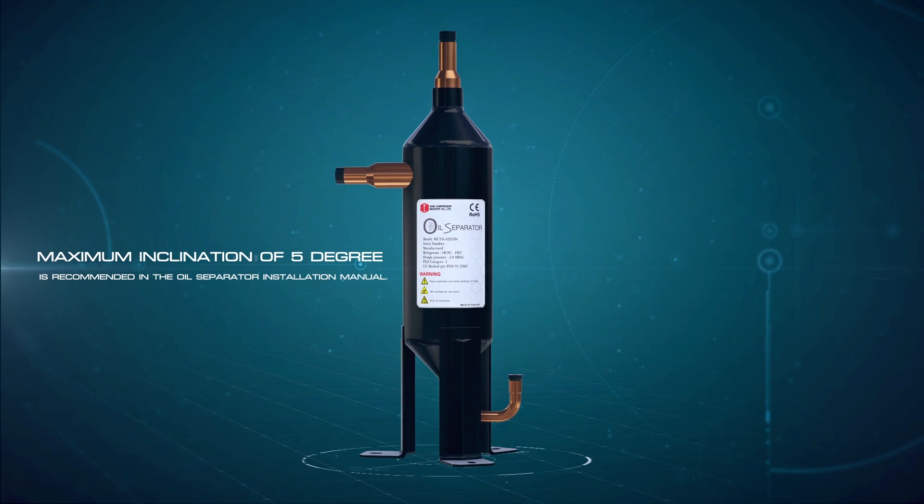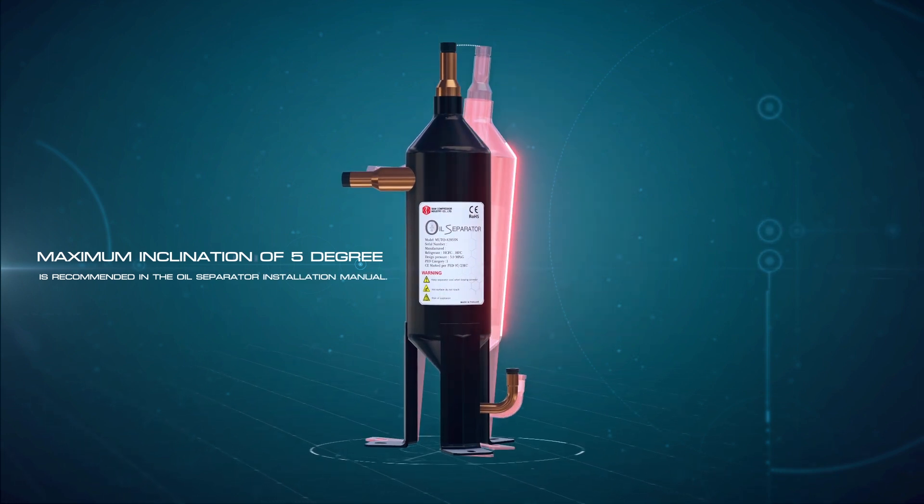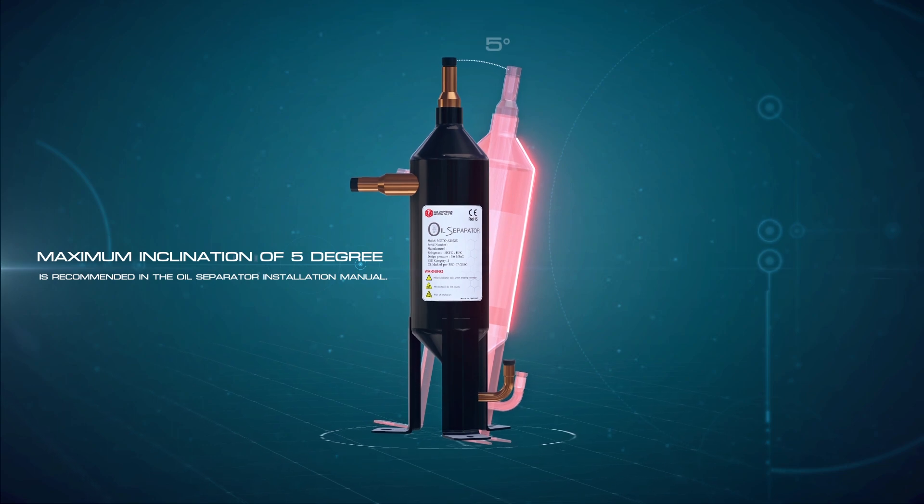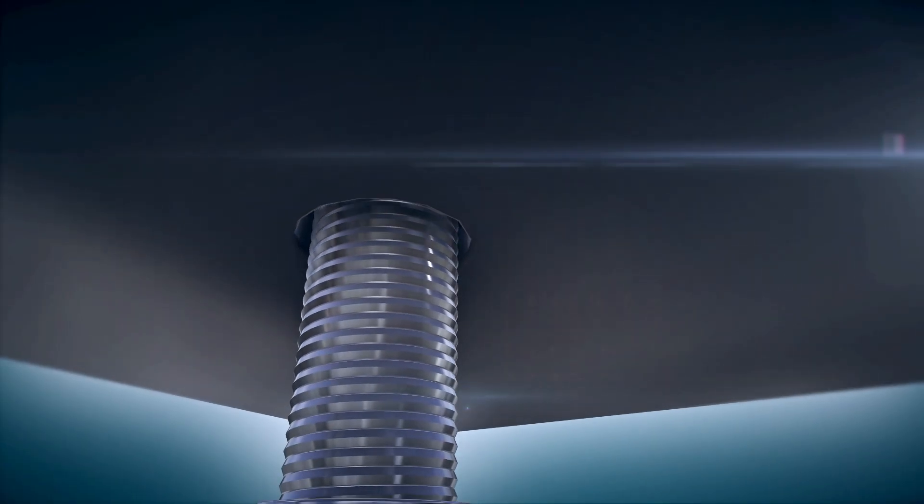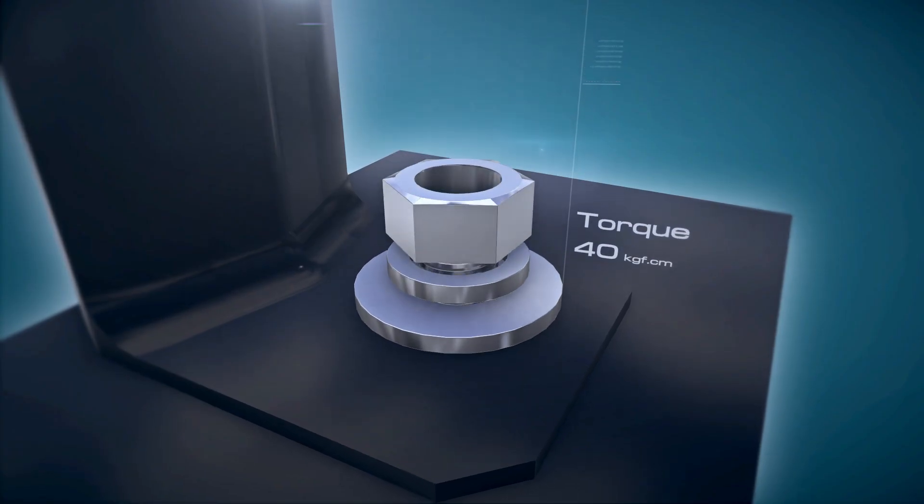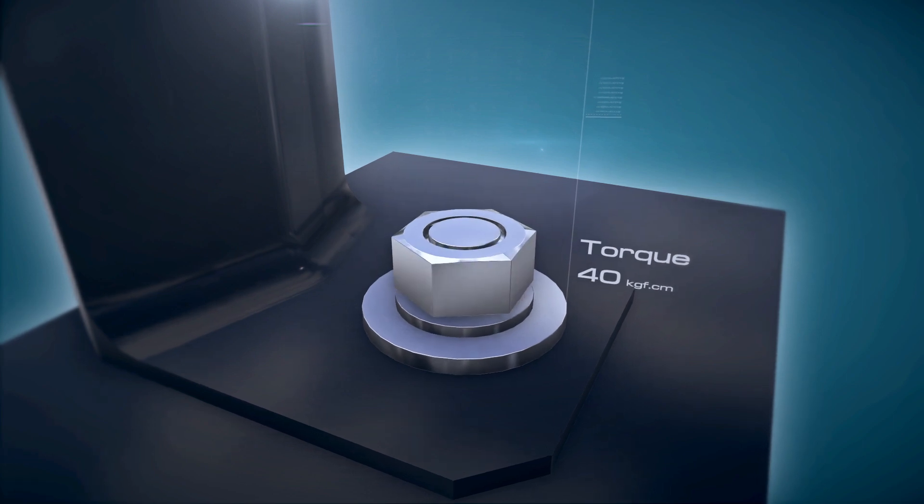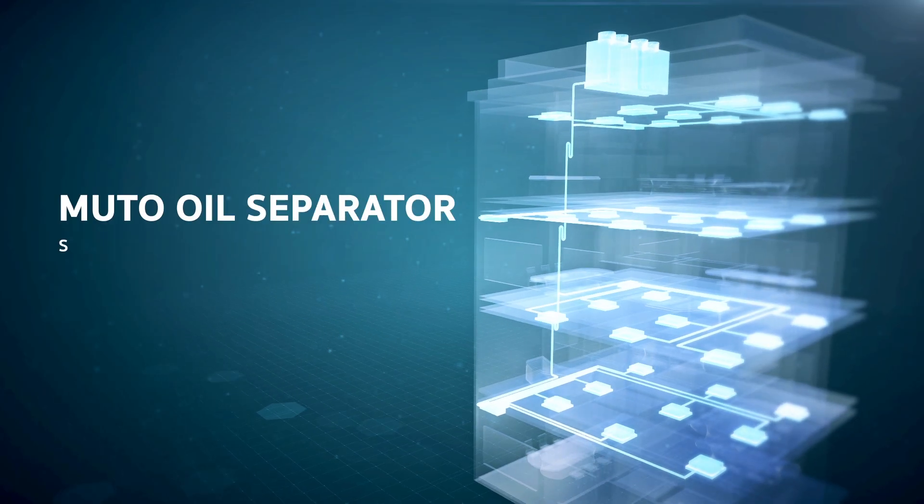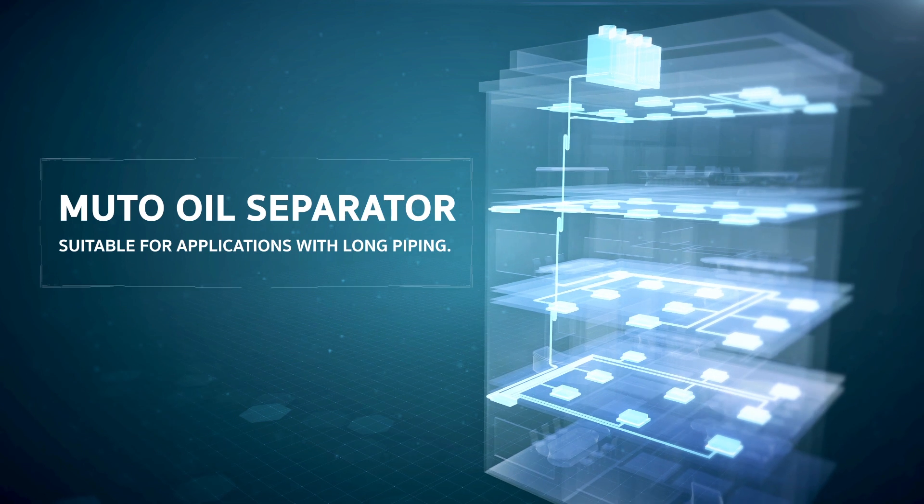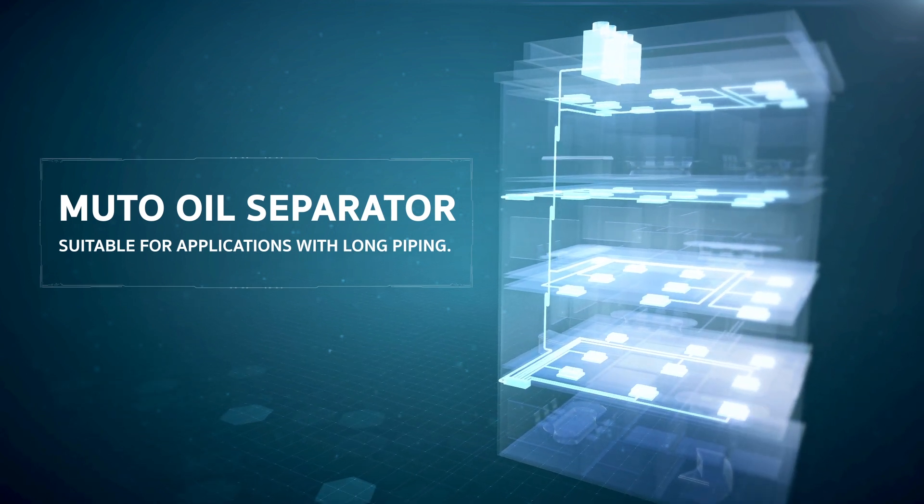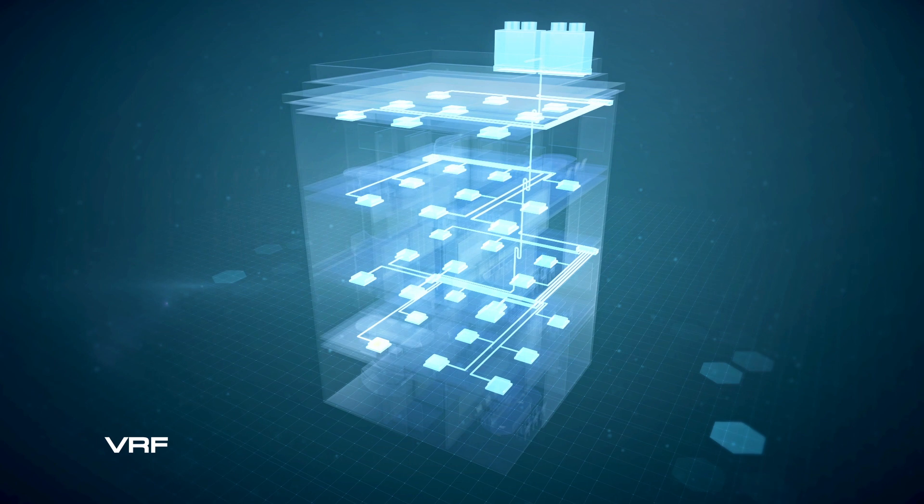Maximum inclination of 5 degrees is recommended in the oil separator installation manual. Specified screw torque on mounting is 40 kgf cm. The MUTO oil separator is suitable for applications with long piping, for instance VRF air conditioning systems.